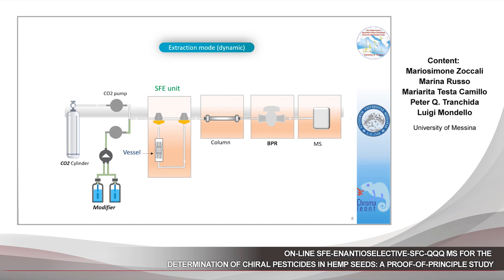This step is called the dynamic extraction mode and is probably the most important one, because we must transfer the analyte from the vessel into the analytical column, and also focus the extracted analyte at the head of the analytical column in order to achieve good separation. At the end of the dynamic extraction mode, both valves return to the original position, thus the entire flow is again directed into the analytical column, through the back pressure regulator, and finally into the MS spectrometer.